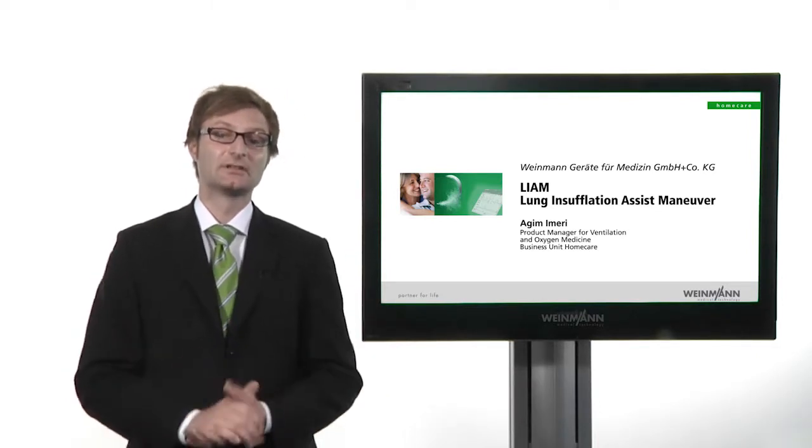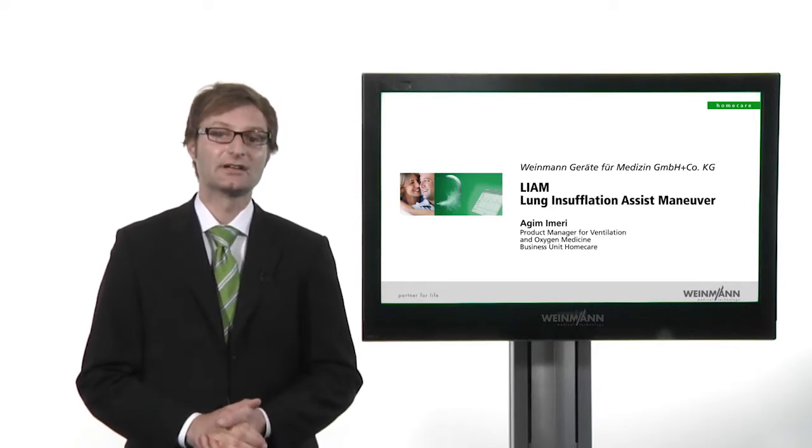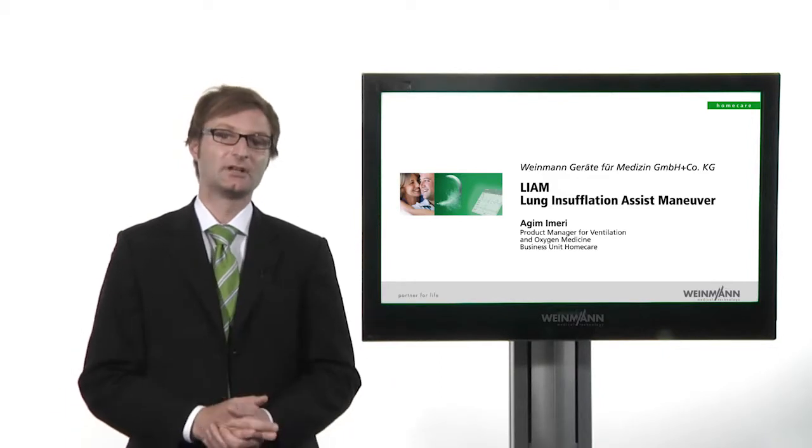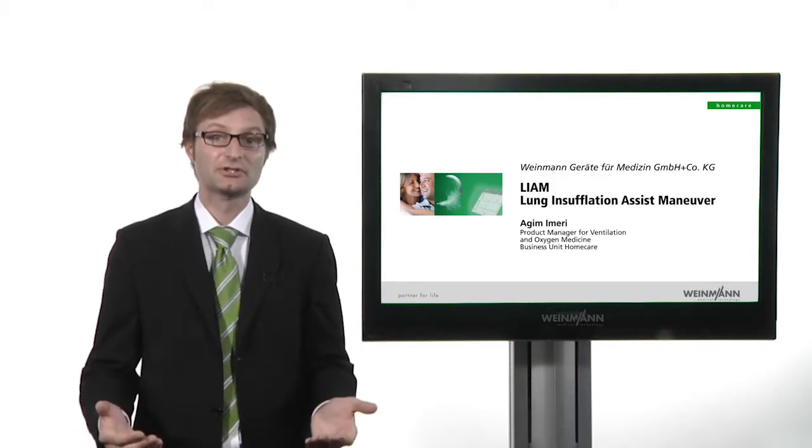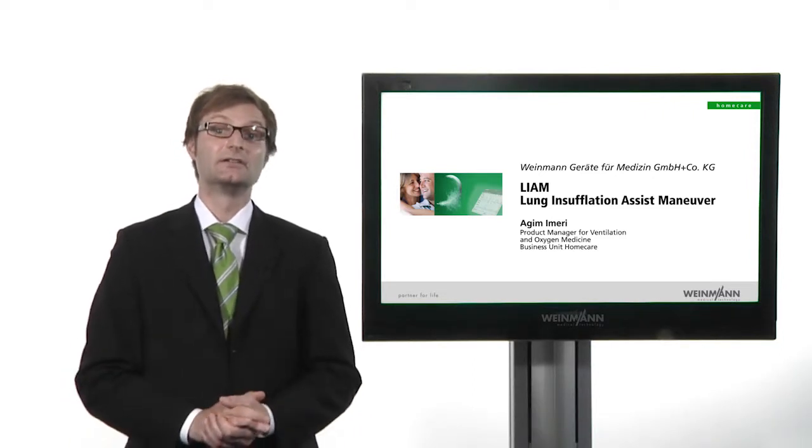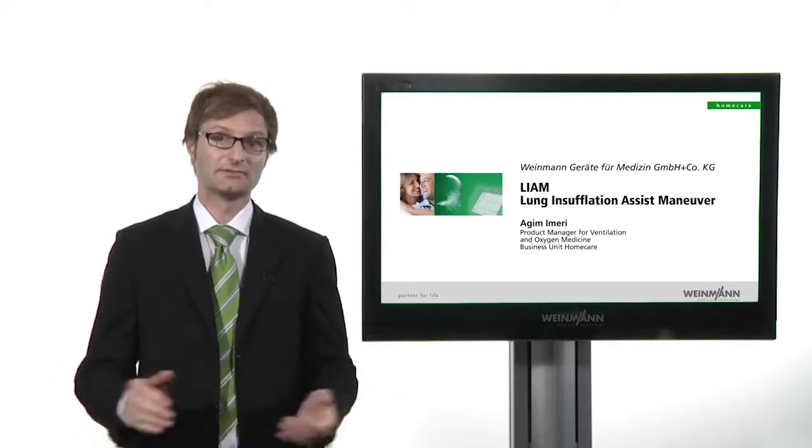LIAM stands for Lung Insufflation Assist Maneuver and was especially developed for treating neuromuscular patients with severe respiratory insufficiency. As these symptoms advance, they cause the inspiratory and expiratory muscles to become so weak that the patient can no longer generate the necessary minimum flow to cough, known as peak cough flow.